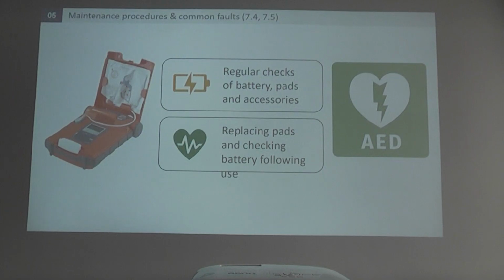For the AEDs, the batteries have a date on them. In that way we will remind you of the date so that you can change the battery. There's also a thing on our defibrillators that shows you how full the battery is. Each battery is rated for about 400 shocks, so it is very unlikely that you will ever run out of charge. But just be aware that you need to check it, because obviously a dead battery won't deliver a shock, but you'll have plenty of warning before that.